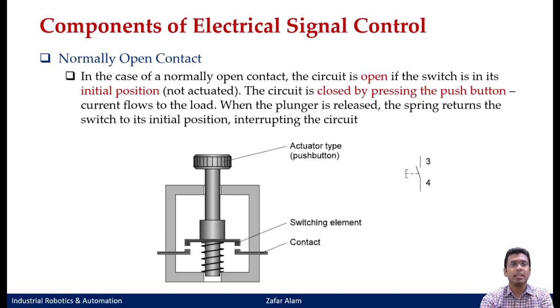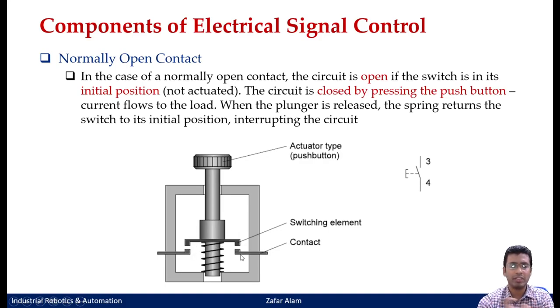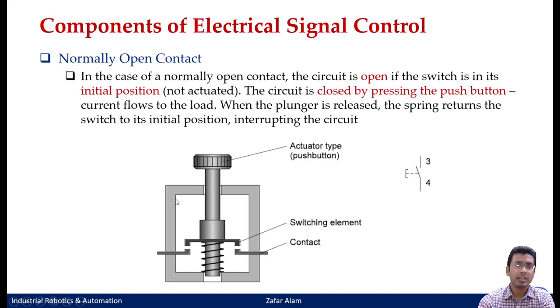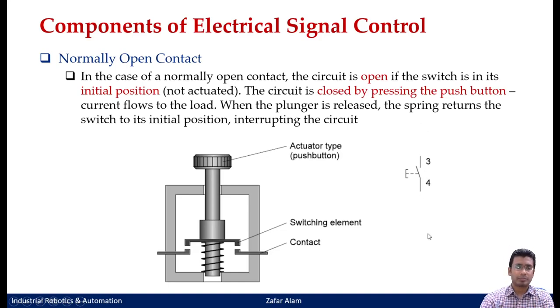Push buttons have only momentary applications — the switch is actuated only for a small amount of time, only as long as you keep the push button pressed, just like your bell switch. Whether using a push button switch or a control switch, both are either normally open contact type or normally closed contact type. In a normally open contact, the circuit is open if the switch is in its initial position. The moment you press it, the circuit gets engaged and current starts to flow.